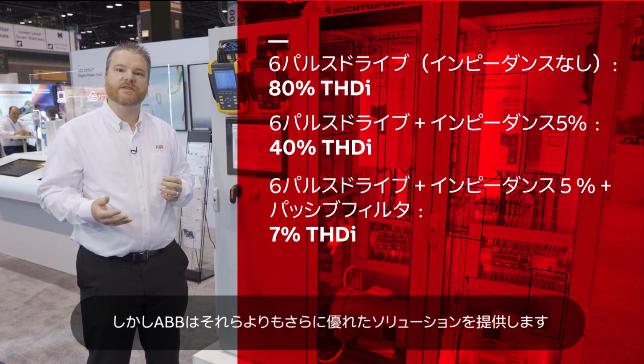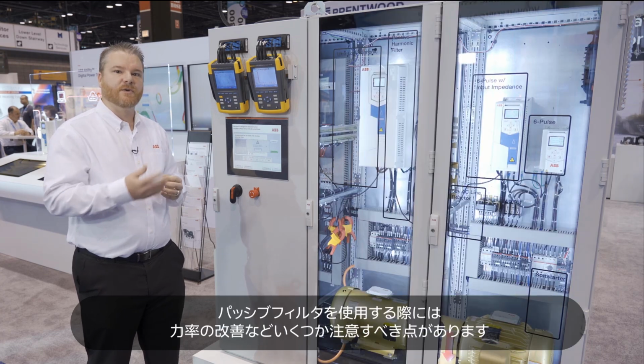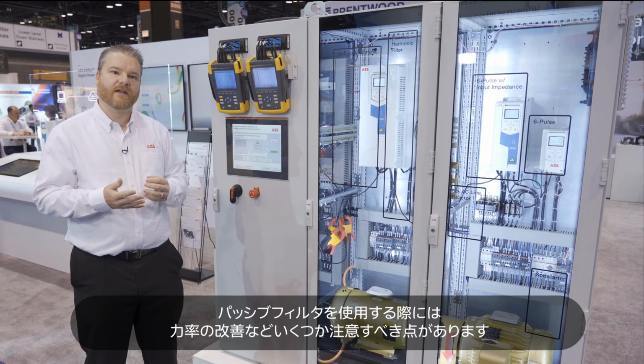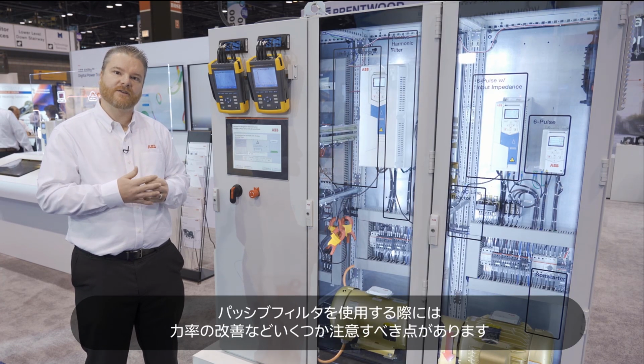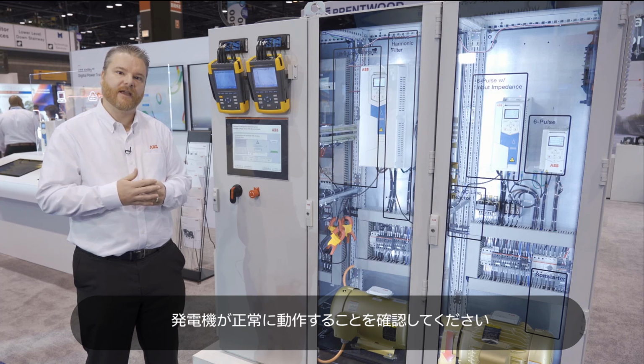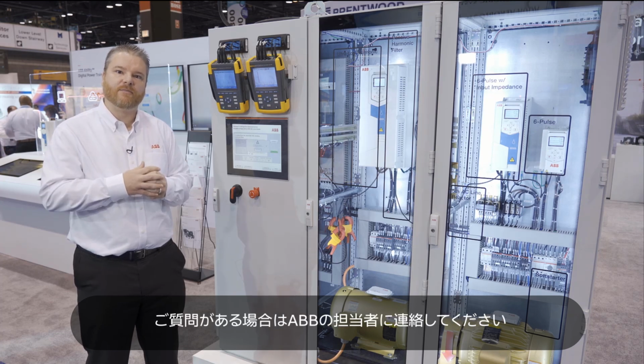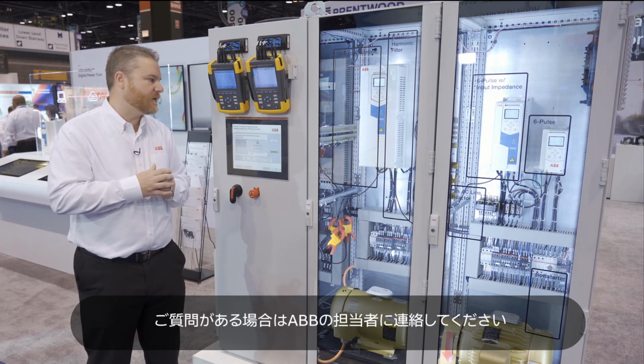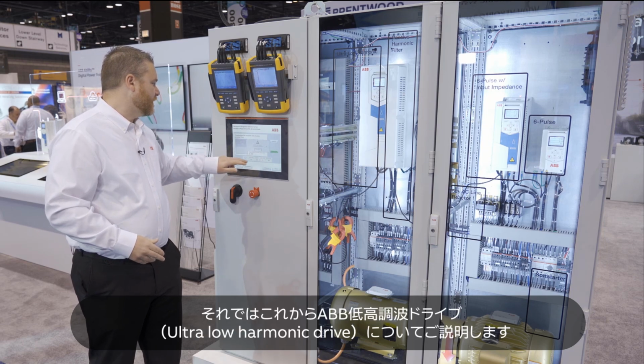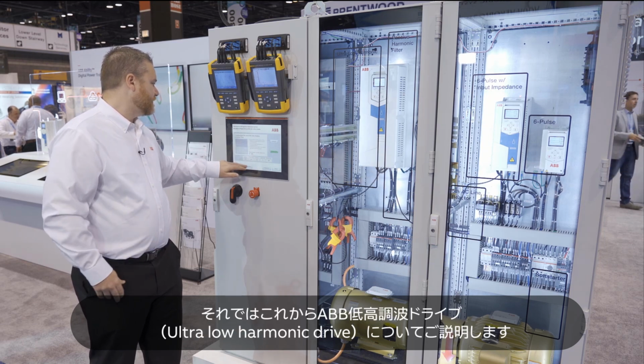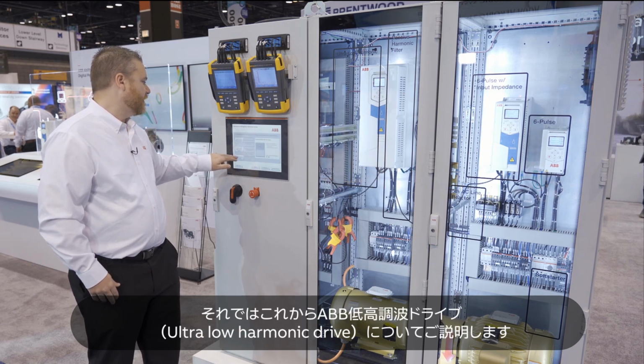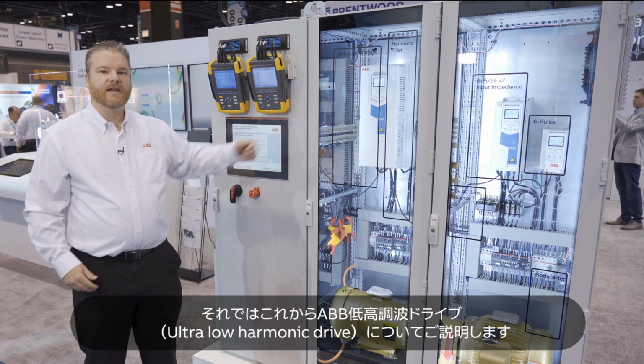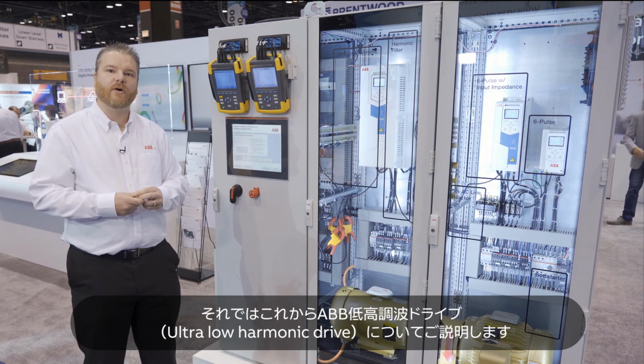But there are still solutions out there that are even better than that. Also with the passive filters, you have to be a little bit careful on things like leading power factor, making sure your generator is going to operate fine. If you've got questions on that, reach out to an ABB expert. They're more than happy to help answer those questions for you. So what I'm going to do now is come over and show the last drive here, and that is going to be the ultra-low harmonic drive.